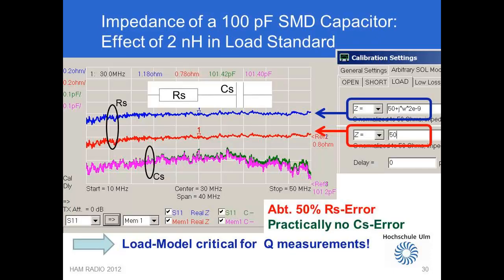On this slide I will show an influence not so widely known. Here I have measured an SMD capacitor of 100 picofarad over a frequency span 10 to 50 MHz with a resolution of 0.1 picofarad. The upper blue and red trace shows the series resistance, which constitutes the loss of the capacitor, and the only trace difference is that the model for the load standard for the red trace is defined to be ideal 50 ohm, while for the blue trace a series inductance of 2 nanohenry is added. 2 nanohenry is a very small amount, less than 1% of the load value.